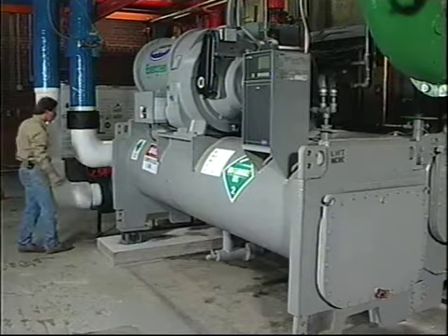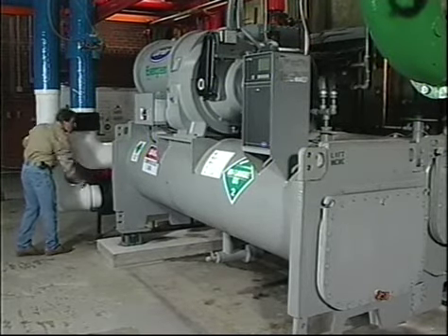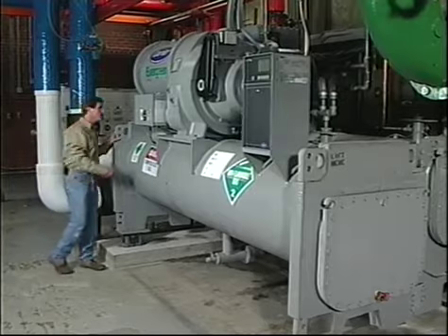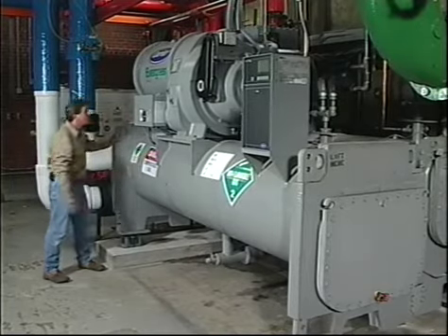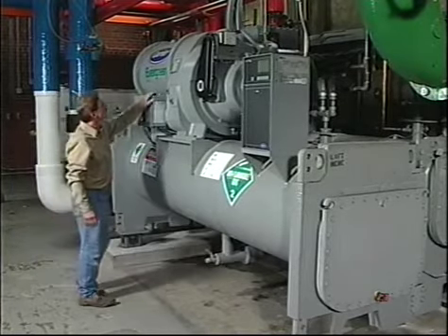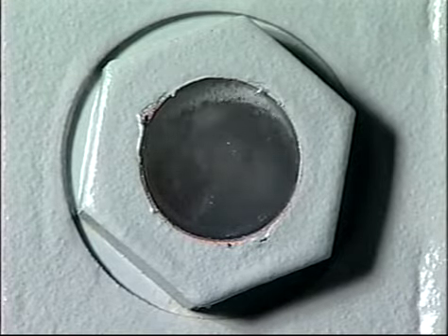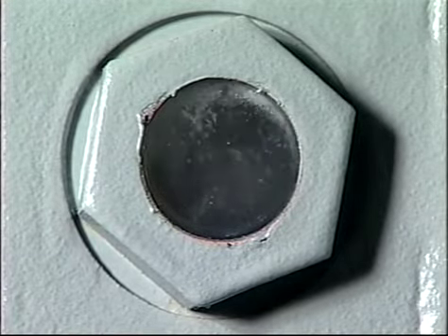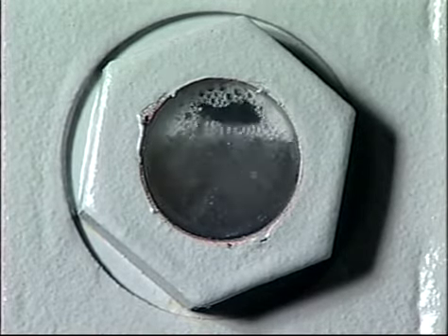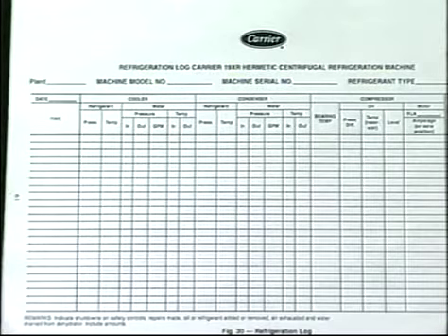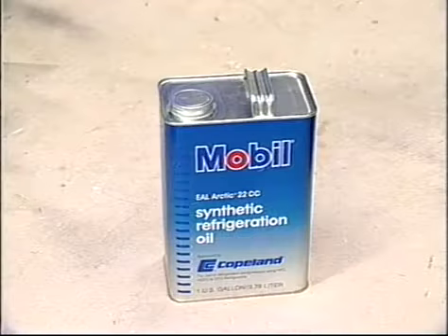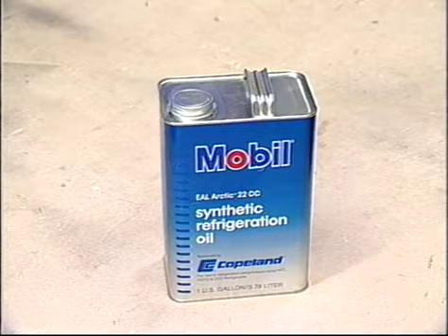On a weekly basis, the lubrication system should be checked. Keep your eyes open for oil leaks. Make sure the operating and shutdown oil levels are within the proper range in the sight glass or glasses, and mark these levels so you can tell if you're losing oil. If you do lose oil, make sure you find the leak and have it repaired. If oil must be added, be sure to record the amount added. Oil specifications are important and vary with the refrigerant used, so be sure that all oil you keep on hand meets the manufacturer's specifications.